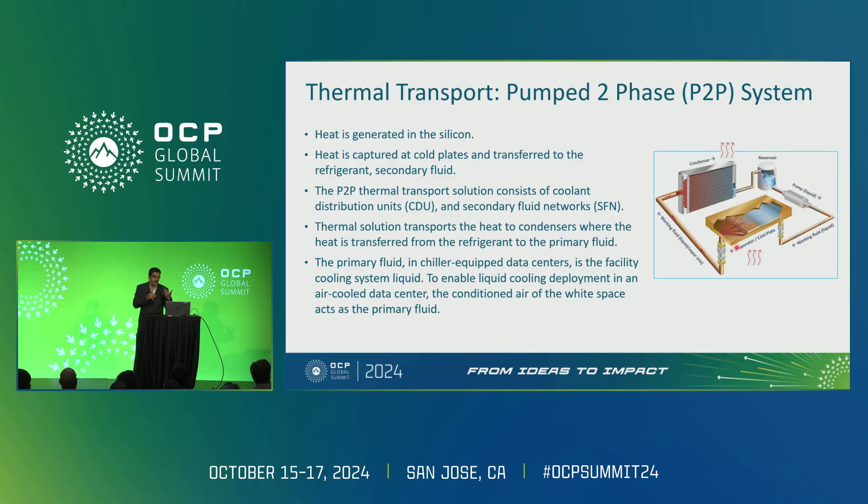The flow rate is set per parallel loop based on your heat load Q, using the equation M-dot times H_fg times quality. As a rule of thumb for low heat flux devices, if you keep your vapor quality less than 70–75%, you should not run into dryout issues. You can set your flow rate such that you never get into dryout conditions, and as long as you are boiling, you should not see an impact on junction or case temperature.